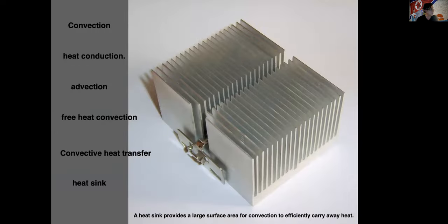And this is actually what is described as a heat sink. In other words, this kind of cell-like series of flat metal planes, I don't know what the word would be, kind of very cellular, almost like a waffle-like arrangement, is to create much more surface area that is interacting with outside air, so that it can actually release heat and cool off. So this is kind of like a heat exchanger that you would find in a lot of air conditioning systems. This is where the heat from the system is released to the outside, and you need to get that heat out in order for the whole system to work as a cooling unit.